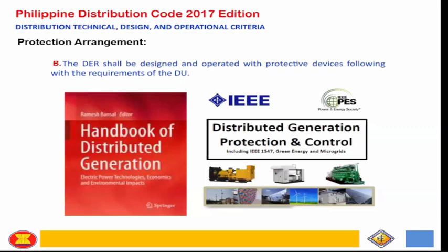Okay? So the DER shall be designed and operate with the protective device following the requirements of the DU. So actually the DU has an established protection philosophy, but the DG side kailangan din mapaliwanagan sa kanila yung requirements, because imagine the practicality of requiring anti-islanding protection na magre-require ng communication, then your DG is rated at maybe 100 kilowatts. Baka mas mahal pa yung facility na nire-require ni DU with respect sa opportunity. Sana yung interest natin, yung mga consumers, it's more on the rate incentives because of this renewable energy. But if the DU medyo strikto, kailangan mag-invest ka, kailangan ma-monitor namin yung na-isolate ka, something like that.